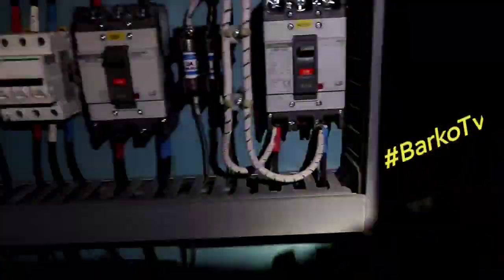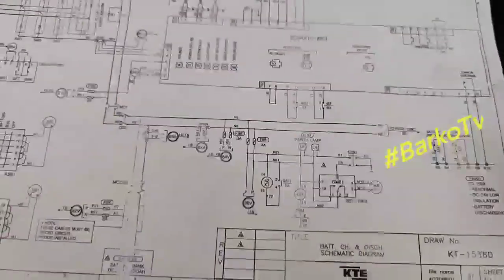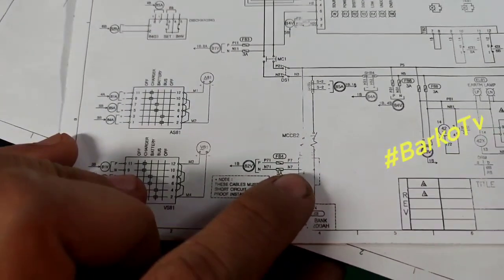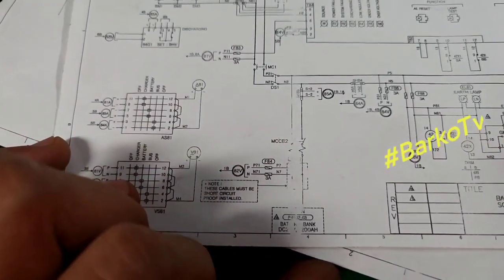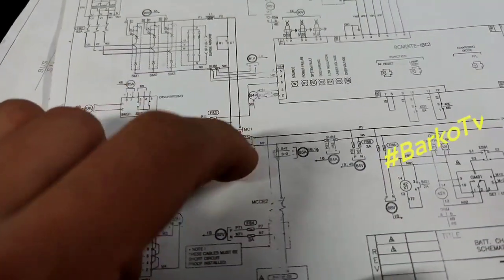If you change the batteries, simply turn off this breaker and then you can change the batteries. This is the diagram for the general service — MCCB2 is the breaker number. If you turn off that one, you can change the batteries easily, because the charger supplies the unit system.